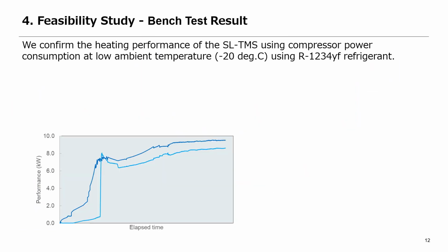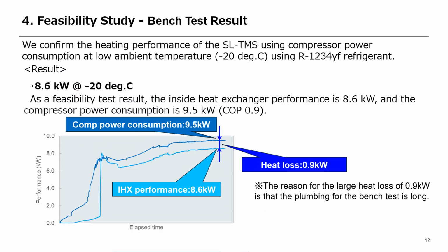This page presents the results from our bench test, where we assessed the heating performance of the SLTMS using compressor power consumption at a chilly ambient temperature of -20 degrees Celsius with R1234YF refrigerant. From the feasibility test, we observed that the inside heat exchanger delivered a performance of 8.6 kilowatts at -20 degrees Celsius ambient temperature, while the compressor power consumption stood at 9.5 kilowatts. This yields a coefficient of performance, COP, of 0.9. Notably, there was a heat loss of 0.9 kilowatts. This elevated heat loss can be attributed to the extended plumbing setup utilized in the bench test.